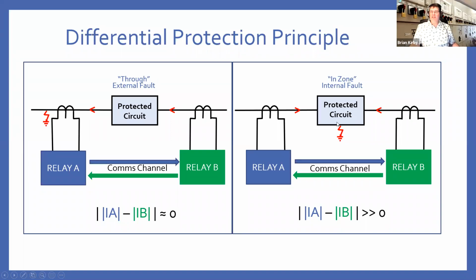However, if you had a fault internally, you see now the flow arrows, this is assuming you have a source at either end. If you had no source at one end, you just have a feed in from one end. But either way, when you compare the measured currents from the 2 ends, you will see your current is significantly larger than 0. So that would be an in-zone fault, and you would operate. Because both ends are measuring locally and receiving remote ends, both ends will see the fault at the same time, but they will also have intertripping capability. So if one end doesn't for some reason see it, it can be tripped by the other end. You may also have intertripping with other devices nearby to switch in local logical schemes to isolate other bits of equipment.